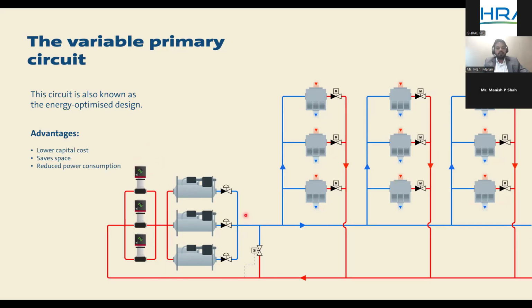And we have a little line here, which is a decoupler line, a bypass line, to ensure the minimum flow. Any chiller comes with a minimum flow which has to be maintained. During the condition where the load is much lower than the minimum flow of the chiller, we fix the speed of the pump so it does not drop below the minimum flow, and exactly the flow needed on the secondary is taken, and the excess flow is bypassed through the decoupler line. That's how we maintain the minimum flow to the chiller, but it compromises a little on the delta T of the chiller side.